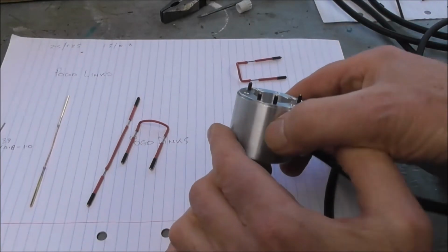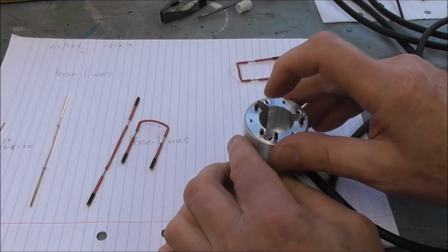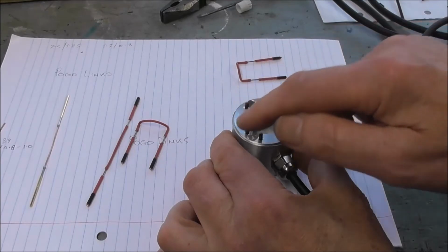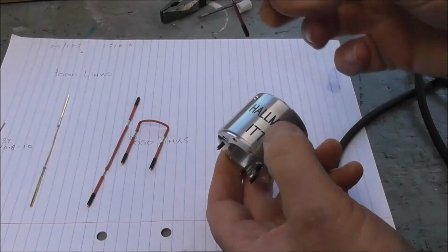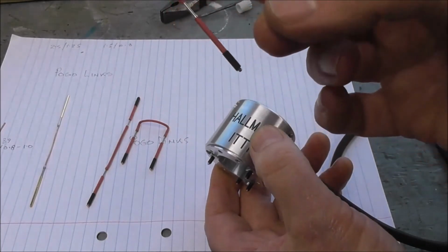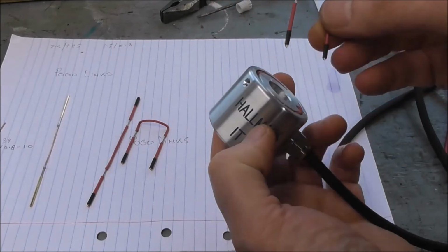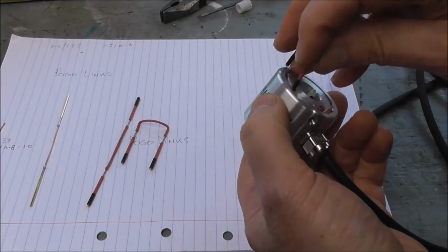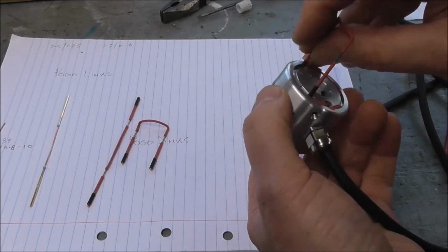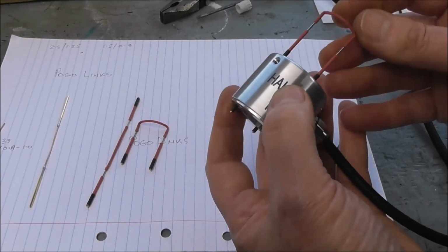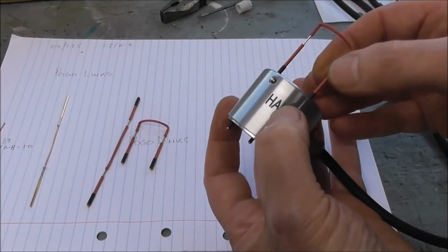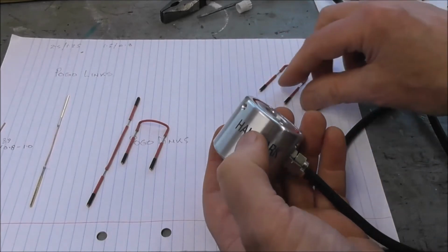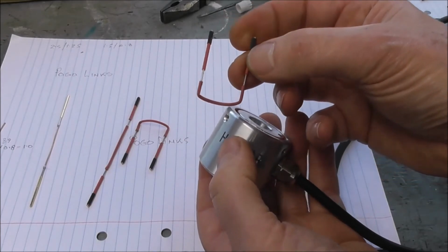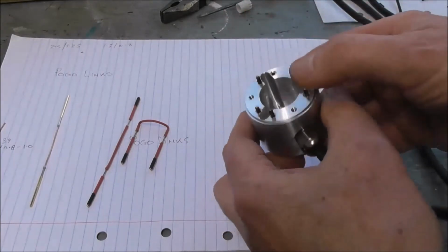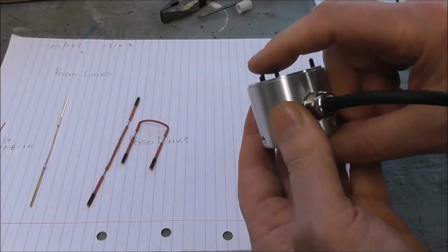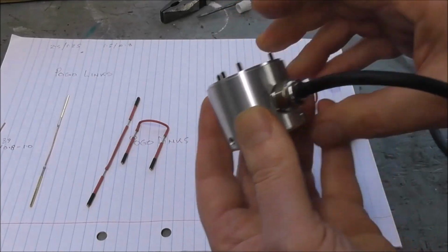And again, check that the little pogos are protruding, and they should spring in and out evenly. If they don't spring in and out evenly, there's something wrong. There's a bias, a misalignment, a lump of solder or something, and it needs to be corrected. Alright, so that's the assembly. Don't do it in a hurry, it's pretty critical work. It's important that there is no broken solder joints. I'll stop fiddling with it while I'm talking. That there's no broken solder joints, that the insulation is intact, and most importantly, the little pogo pins are all free to spring in and out to make contact with the balls.